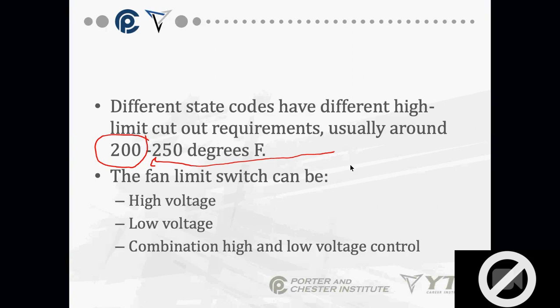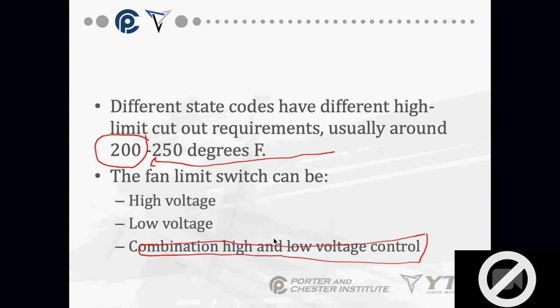It can all be on your high voltage side, it can be on your low voltage side, or it can be a combination of high and low voltage. I personally like to see it on the low voltage side, but I'm seeing a lot of them coming from the factories as a combination right now of the high and low voltage. Again, because of the digital thermostats. High voltage only, those are getting older and older. We don't do that often anymore. There's too many problems there.